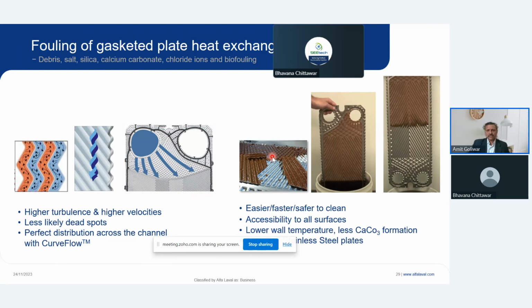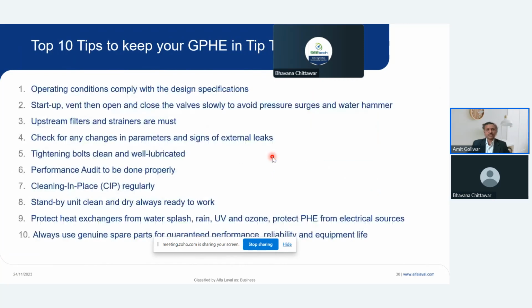With this, I would like to present some tips to maintain the heat exchanger in a better way. First, the operating conditions should comply with the design specification. Use the heat exchanger for the application you designed it for and asked the heat exchanger for. At the time of startup, it is very important that valves should be opened very slowly. Otherwise, there will be water hammer and pressure surge problems, damaging the heat exchanger.